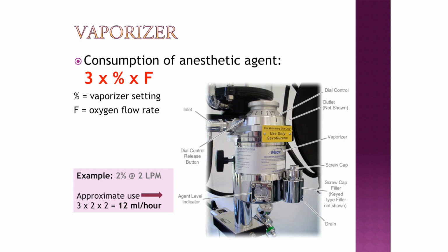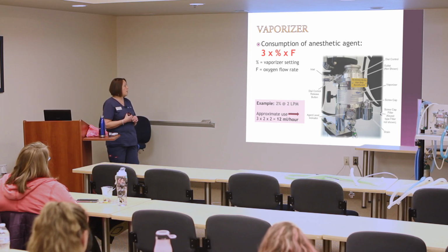And then the one machine in OR1, the blue EVAD machine, you do have to be really careful when you activate the dial on the vaporizer that you push the button down here first. He wants you to use 2 hands, push the button, and then open it. We actually already had to have a repair done on that because this got bent and the vaporizer wasn't really working properly. So do be careful about that.